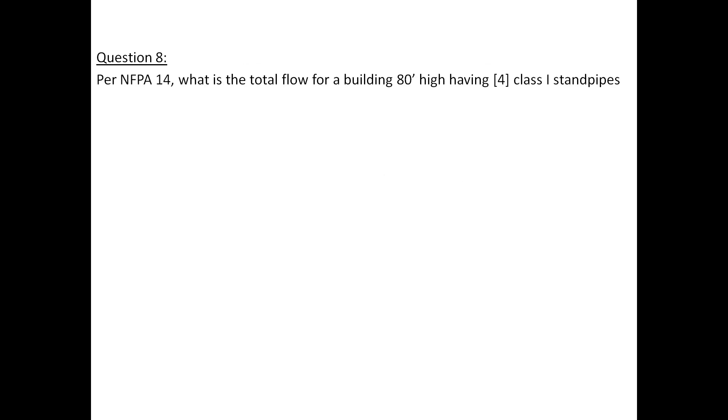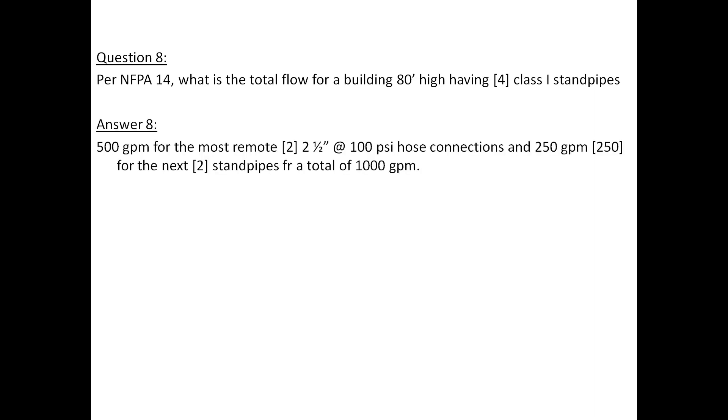Question 8: Per NFPA 14, what is the total flow for a building 80 feet high having 4 class 1 standpipes? Answer 8: 500 gallons per minute for the most remote 2 2.5 inch at 100 PSI hose connections and 250 GPM for the next 2 standpipes for a total of 1000 GPM.